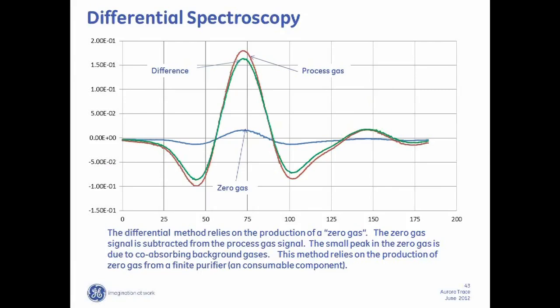And the other issue with this is that you have to take the measurement offline to dry out the sample. With the vacuum system, the system can go online 24/7. And should the vacuum pump ever fail, there's a pressure sensor that monitors it. You'll get an alarm. With this, you're reliant on having a good, effective purifier, and that purifier is many times a finite column. So as that absorbs water and breaks through, you don't know until you see a peak on the zero gas. So we feel that there's several advantages to the vacuum system versus the differential spectroscopy that's traditionally been used.